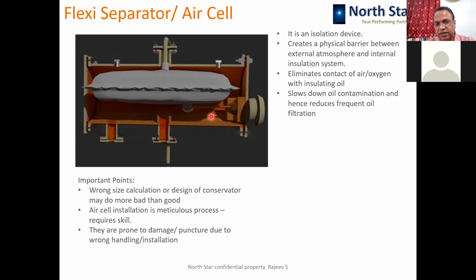But these air cells also have their own set of issues. Many times it is found that because of wrong design size calculation, they are either too big or too small, so they won't do the function rightly. Air cell installation is a meticulous process. It requires skill. So sometimes, if the air cell gets discharged, the charging of the air cell has to be done by skilled people. So we do all these activities at site. We have our people who do this air cell maintenance.